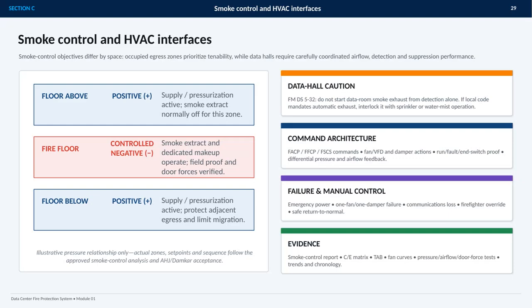This section focuses on the interfaces between smoke control and HVAC, where the right strategy depends on the space being protected. In occupied egress areas, the priority is tenability, maintaining conditions that support safe evacuation. In a data hall, airflow, detection, and suppression must be coordinated much more carefully, because an exhaust response can affect both smoke movement and fire protection performance.